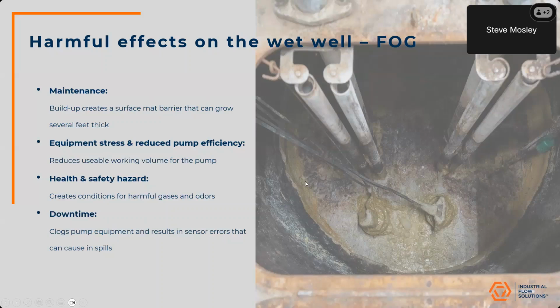Next topic we want to talk about is the fats, oils, and greases, the FOG layer that develops on the top of the wet well. This buildup creates a surface layer on the top of the wet well that can grow up to several feet thick. In that layer, you'll commonly find the float switches or level transducers, and as that fat builds up on those components, it can cause the float switches to fail and not turn on the pumps, which will eventually cause an overflow if not dealt with in an appropriate time frame. It is a health and safety hazard, and it does cause some pretty bad odors in areas where you've got a significant amount of fats and greases that are sitting in that wet well.